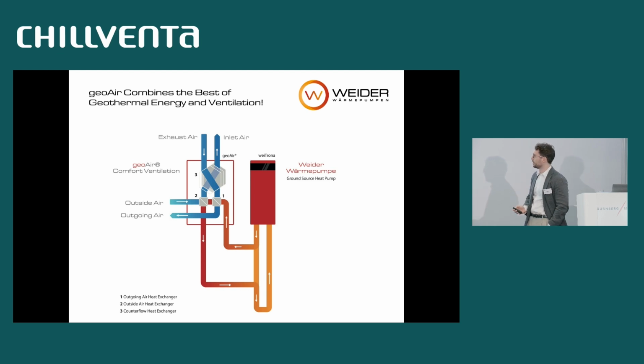But also in winter, when the outside air is cooler than the brine itself, the brine actually heats up the outside air, and freezing will be prevented in the third heat exchanger, the air-to-air heat exchanger, and the inlet air will also be warmed. So this is more an improvement of comfort, because some people argue that on cold days, the inlet air is also too cold. And the geoAir also doesn't work with additional heating elements, so the efficiency is improved.